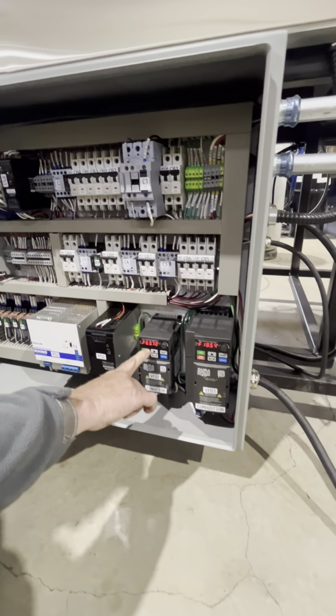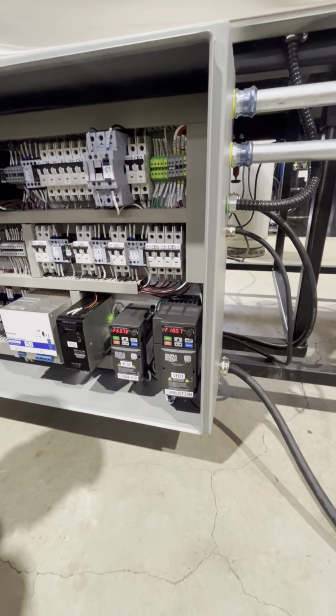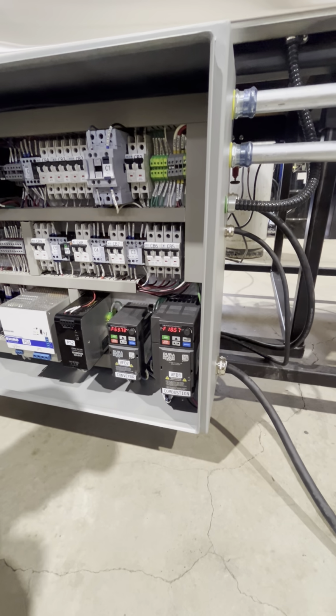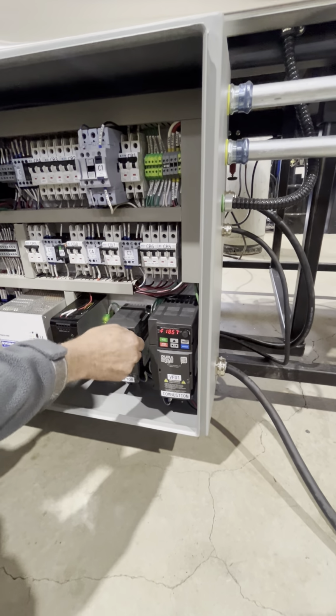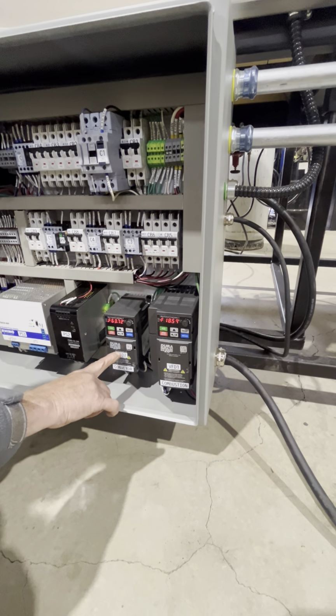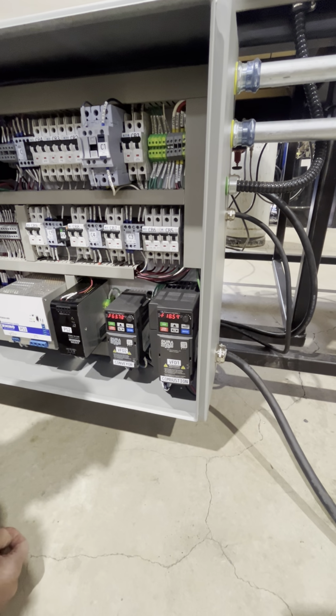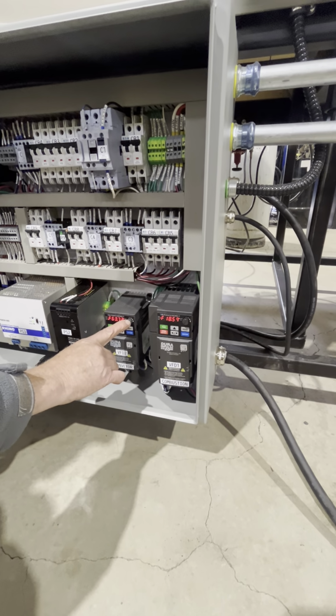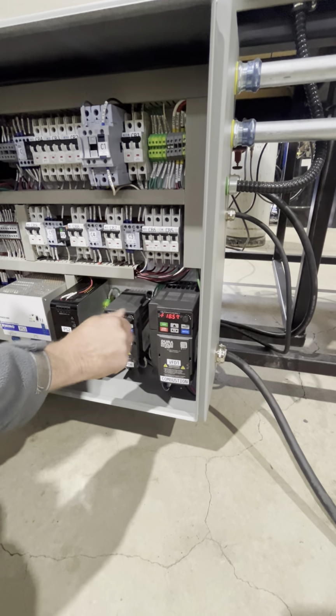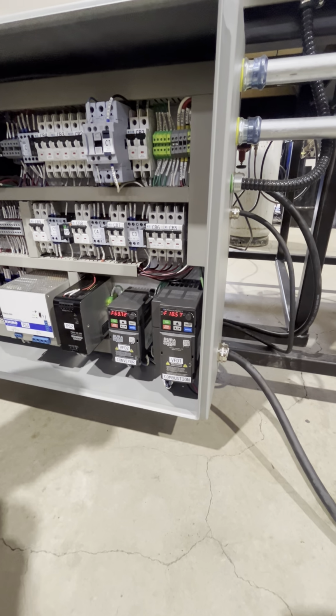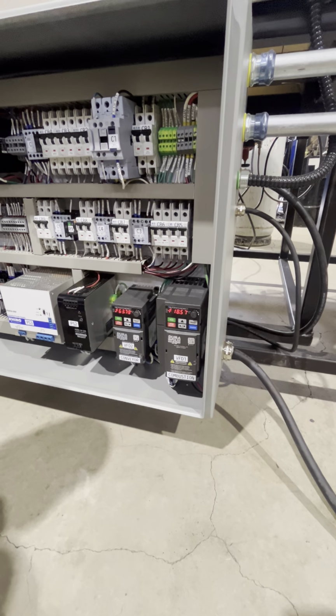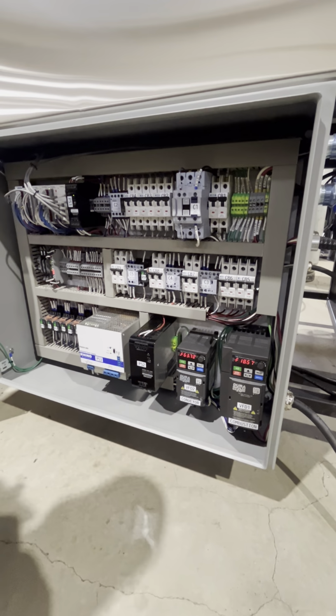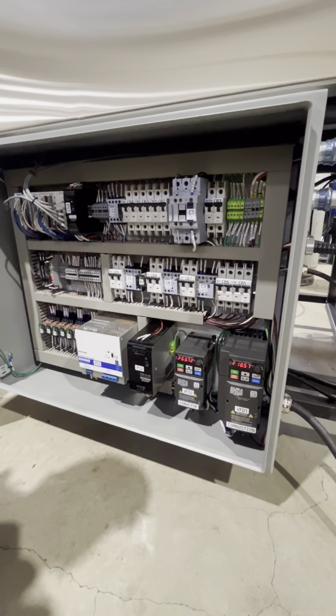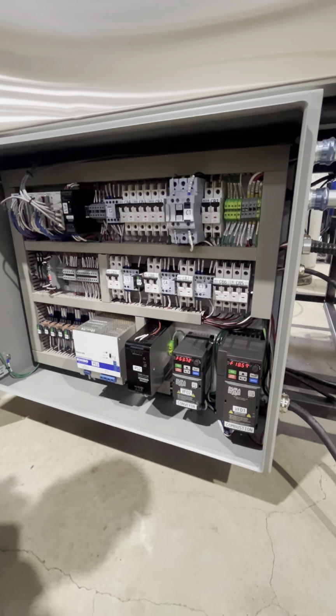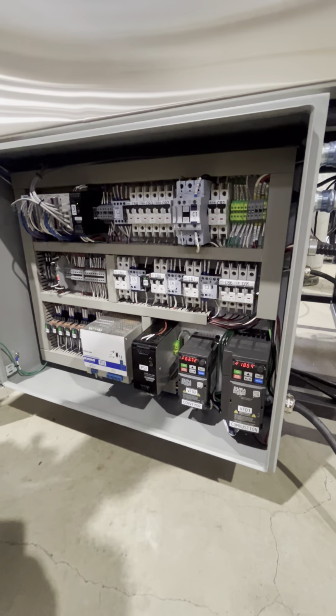The VFDs have a frequency that they're set at. That frequency is based off of the input on the HMI. So it has a knob here to adjust it. However, because of the way that we have it jumpered inside, and it's according to the instructions on the VFD, you can have this operated locally by this knob here, or you can have it remotely. We have it wired for remote off of the HMI. So that's basically what I can give you in a basic overview. If you need more than that, then I think you might need a qualified electrician and to look at the wiring schematic, okay?